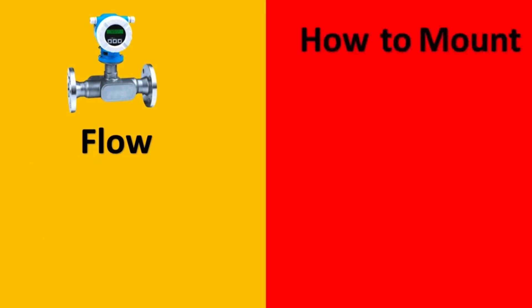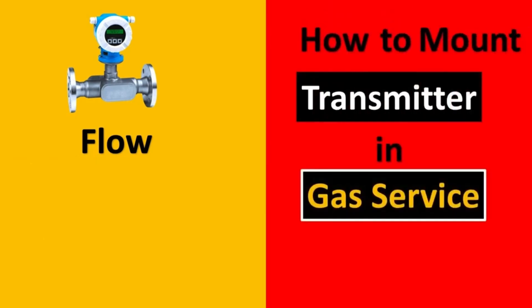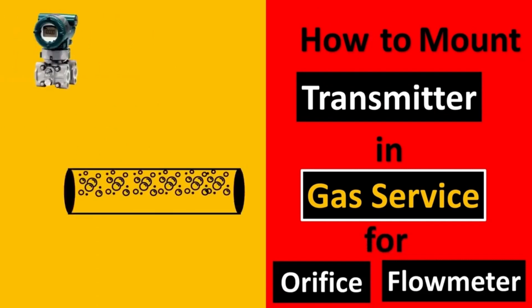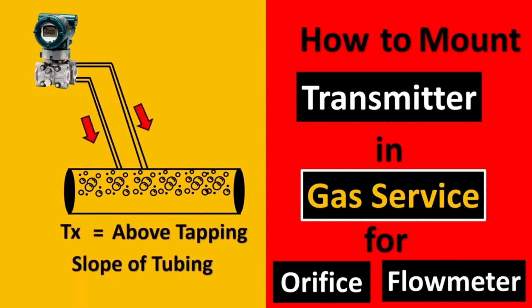In flow, one of the most asked questions is how to mount the transmitter in gas service, especially for orifice flow meters. Let's take this example: here's your pipe and here's gas flowing through it. Now the transmitter is put on top of the pipe or top of the tapping, and the second important thing to note is that the slope of the tubing has to be towards the pipe.